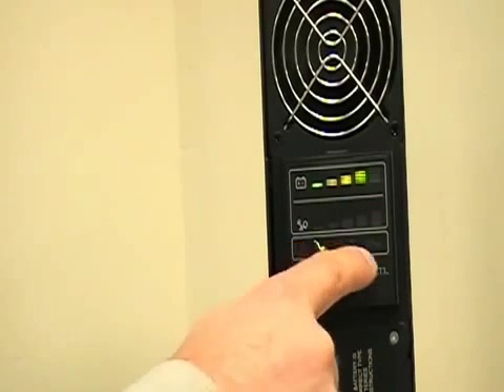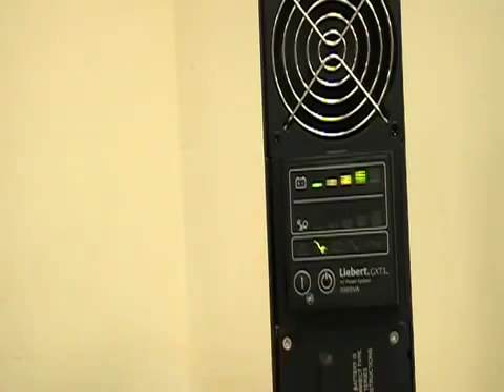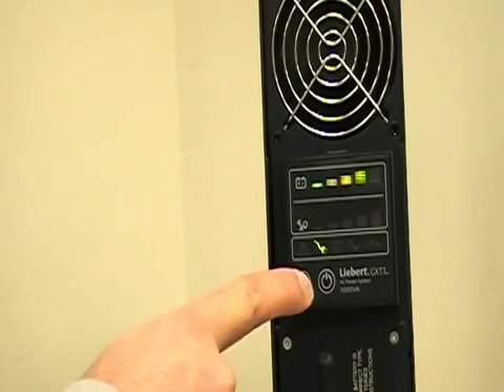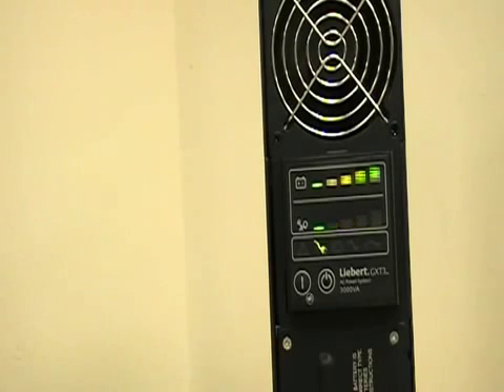But you'll notice all I have is an input. I don't have any AC output, and I'm not on bypass. I have to go ahead and transfer it back online, press and hold that for a second. The unit will ramp up, take about a second, transfer to bypass, and then it'll go right online.